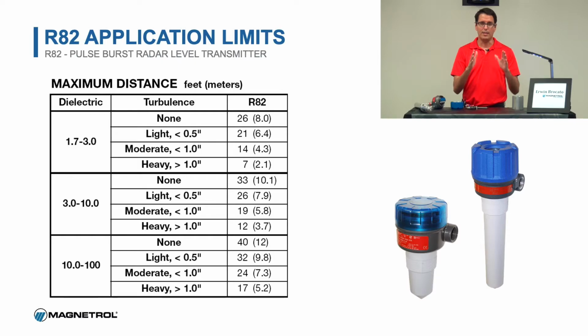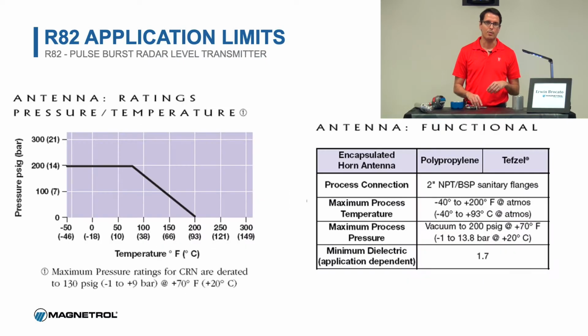Obviously, there are going to be different limitations for the different products. In this chart that you can see here on the presentation, on the right, it'll tell you how far the unit can go based on the different disturbances and dielectrics of the products. If you have water, which is a dielectric of 80, way at the bottom, and there are no disturbances, you can go up to 40 feet, no problem, you get a good reflection. But if you have maybe a crude service and you have heavy agitation, you can only go down to 7 feet. You can't really hit that product as well with this device. Now, again, we have a higher-end model that could probably do it a little bit better if you have those conditions. So this is for easier services, let's say, for this particular product.